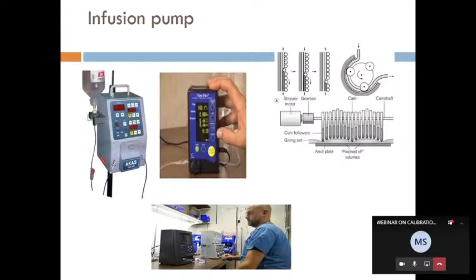So with the help of this analyzer, you can measure. Instead of connecting to the patient, you connect the output tube to the machine, and the same tube can be taken out from the analyzer and put in a beaker. The beaker volume, the machine volume and the infusion pump volume should all be the same. Once they are the same, the machine is calibrated. For example, if the pump is delivering 100 ml, the analyzer has to show 100 ml. The same 100 ml has to come out from the analyzer into the beaker. Beaker 100 ml, analyzer 100 ml, and infusion pump 100 ml. Everything should be the same. If it is showing a wrong value, we need to adjust electronically inside the machine. This is the method of calibrating the infusion pump.